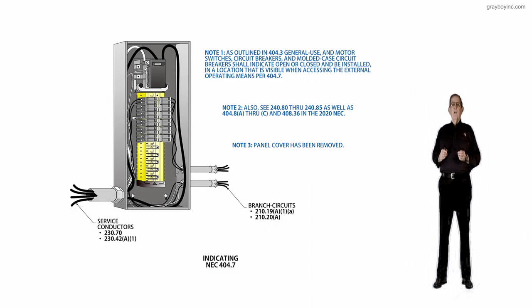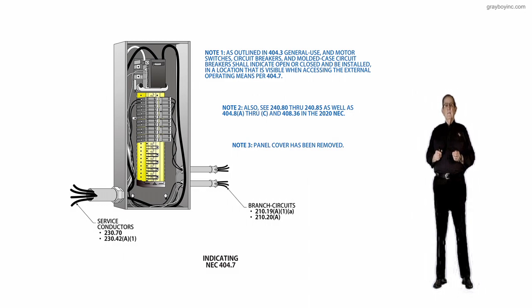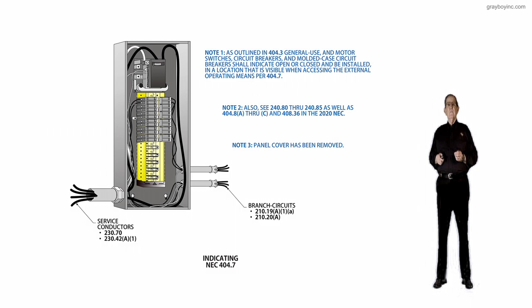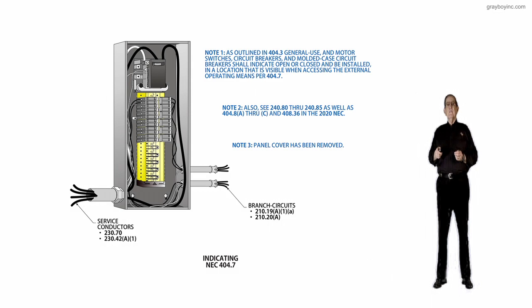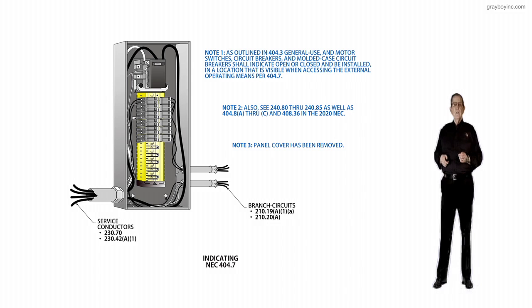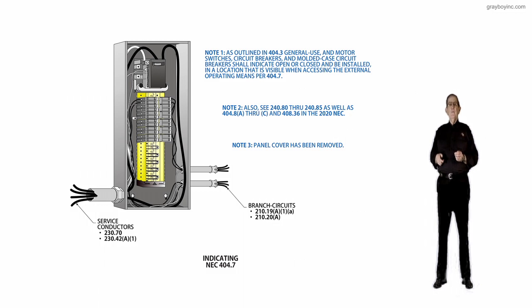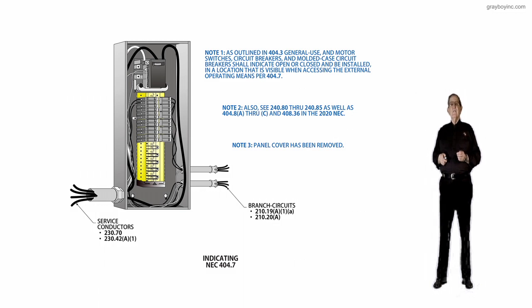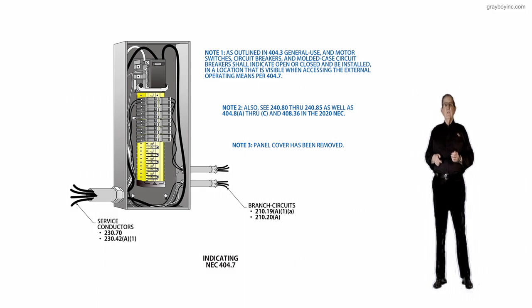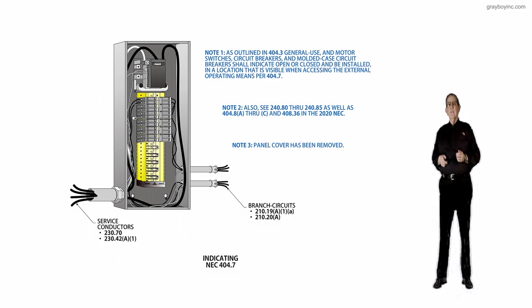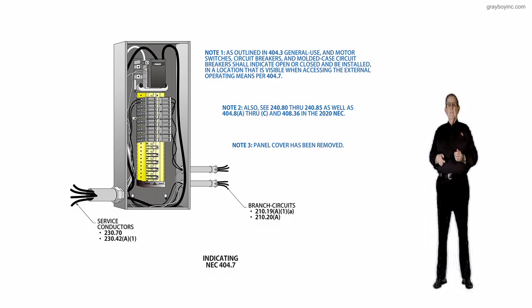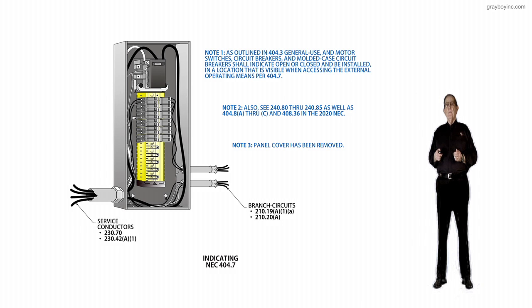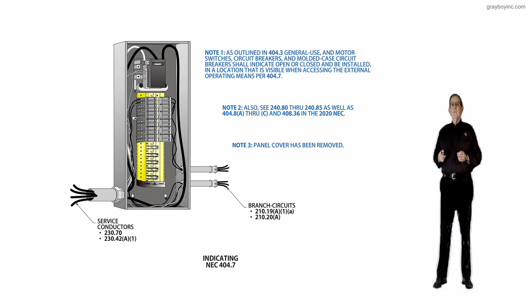First of all, we see the service entrance conductors to the left of this panel board. We know 230.70B allows this single main here. And 230.42A1 sizes the conductors based on continuous or non-continuous load. On the load side to the right where you see the circuits going out in the conduit, these are branch circuits.